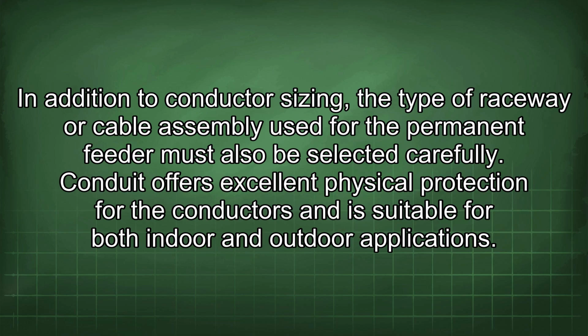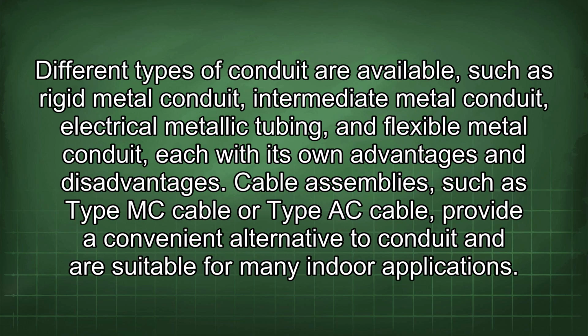In addition to conductor sizing, the type of raceway or cable assembly used for the permanent feeder must also be selected carefully. Conduit offers excellent physical protection for the conductors and is suitable for both indoor and outdoor applications. Different types of conduit are available, such as rigid metal conduit, intermediate metal conduit, electrical metallic tubing, and flexible metal conduit, each with its own advantages and disadvantages.